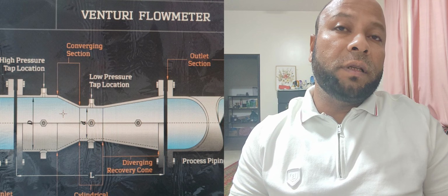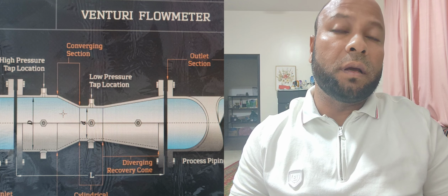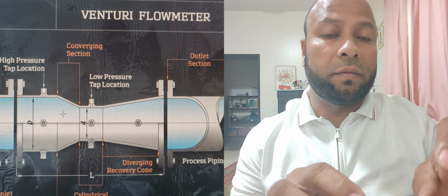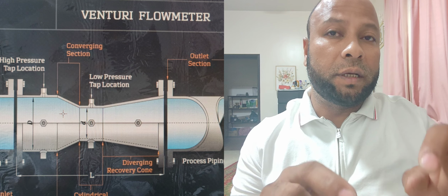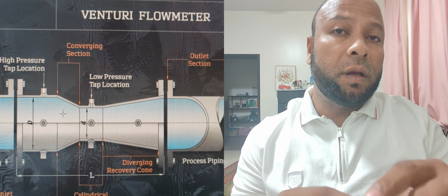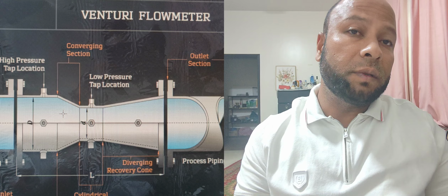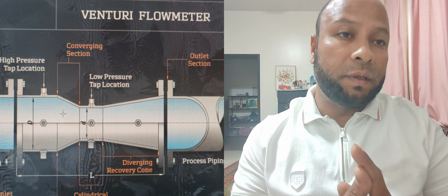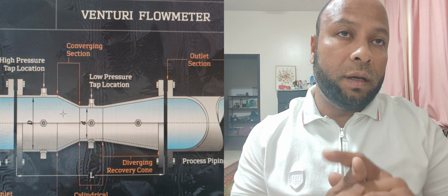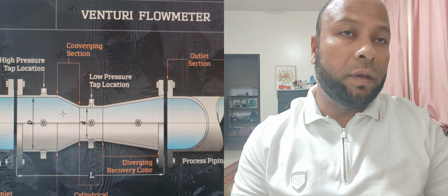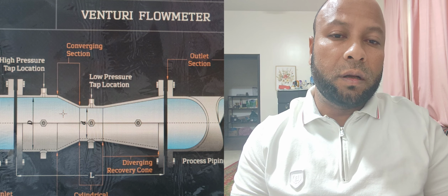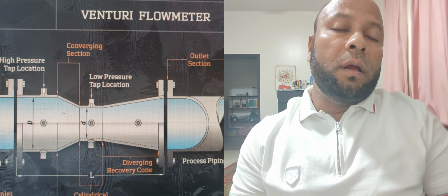At first, the concern was the distance from the tapping points of the tube, high tapping and low tapping, to the transmitter. It was around 20 meters away, at the intake of the turbine compressor.